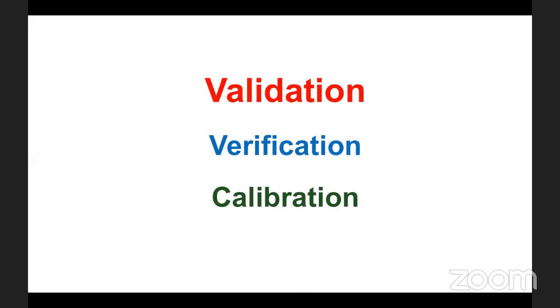So all these measurements should be correct. How can we have confidence in the measurement? When we are getting that checked by authorized people. Who are authorized people? All these non-analytical instruments shall be calibrated by a calibration lab which is accredited as per 17025 for the calibration of that particular equipment.